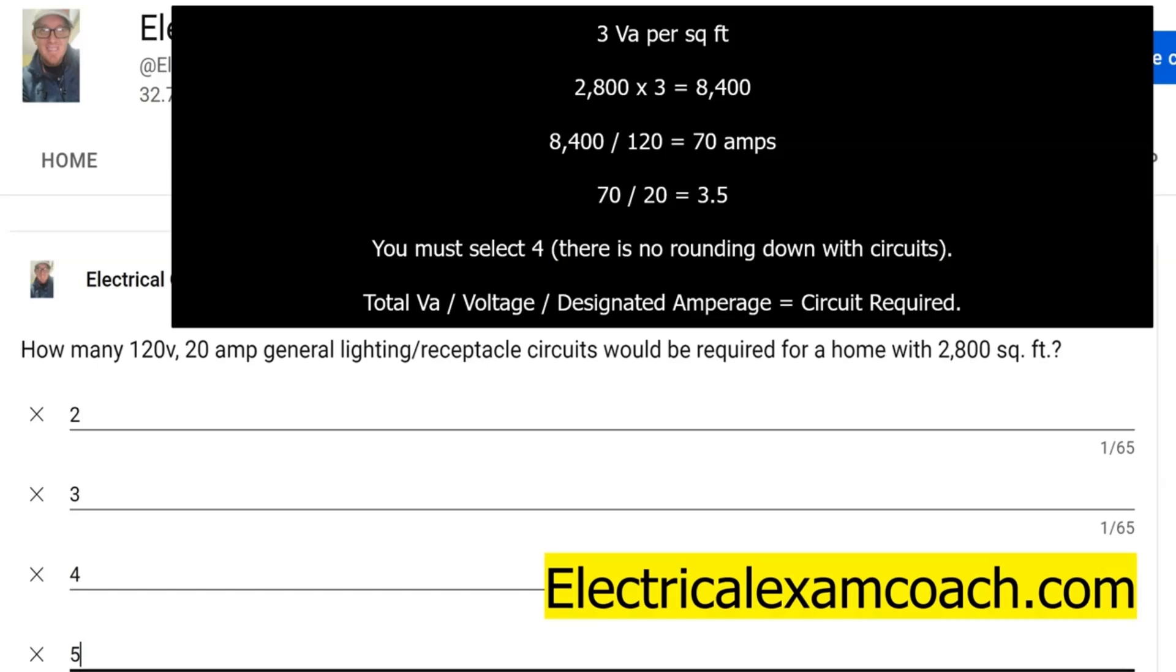Then we take that 8,400 and divide it by the circuit's voltage, which in this case is 120 volts. Then we take that, which is 70 amps, and divide it by the size of the circuit that we're wanting to do. In this case it's a 20 amp circuit, but if it was a 15 amp circuit you would divide by 15 instead.